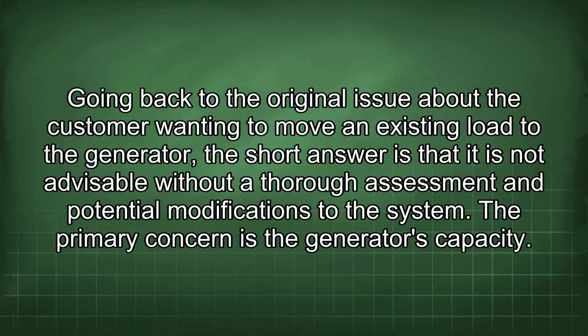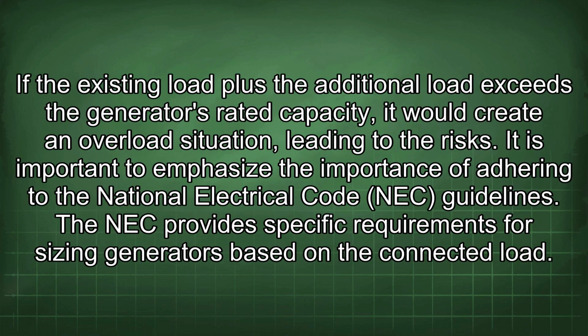Going back to the original issue about the customer wanting to move an existing load to the generator, the short answer is that it is not advisable without a thorough assessment and potential modifications to the system. The primary concern is the generator's capacity. If the existing load plus the additional load exceeds the generator's rated capacity, it will create an overload situation, leading to the risks. It is important to emphasize the importance of adhering to the National Electrical Code (NEC) guidelines.